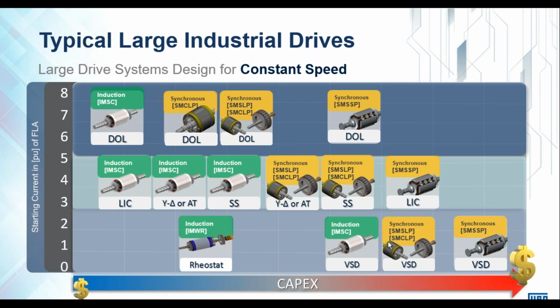And then, as I mentioned on the previous slide, we can use a synchronous motor in conjunction with a VSD. Obviously, this becomes a very expensive solution, and your reactive power control is very limited because it is in fact now controlled by the VSD and not by the synchronous machine.